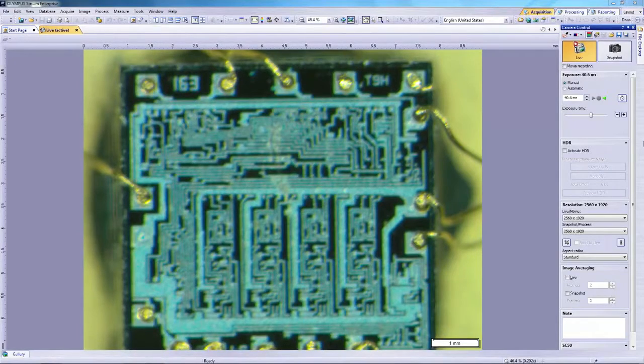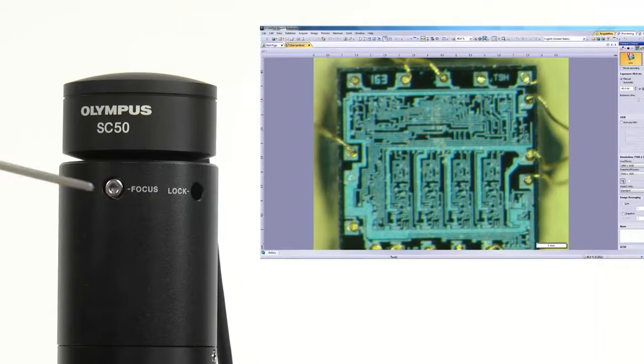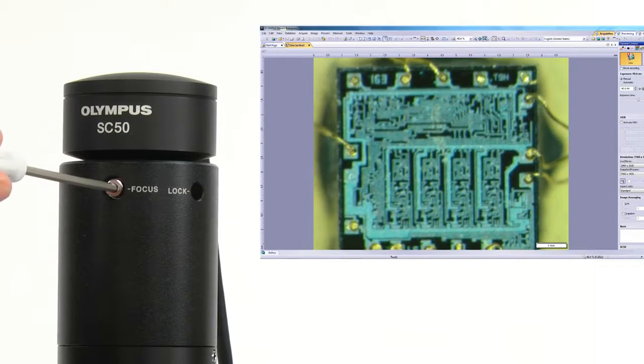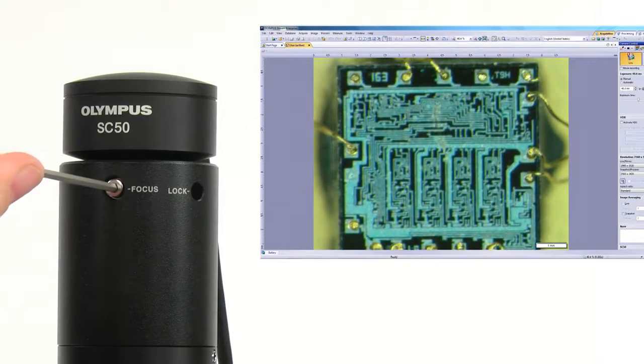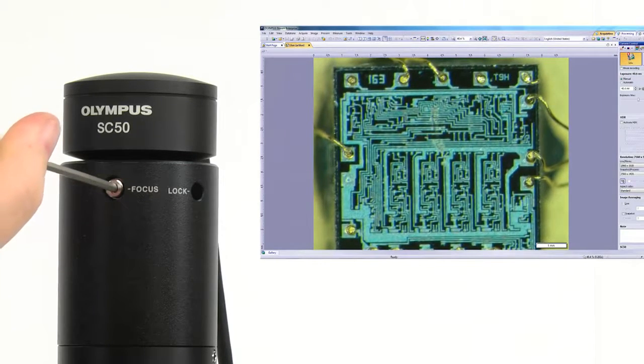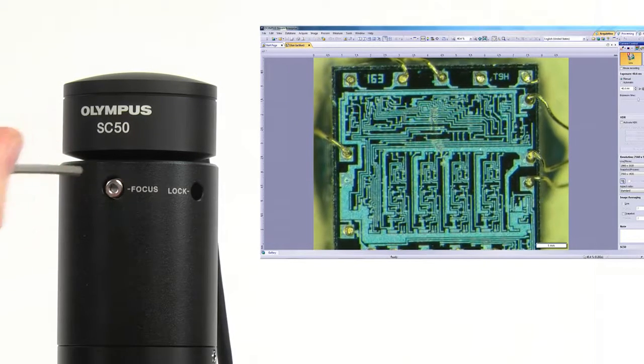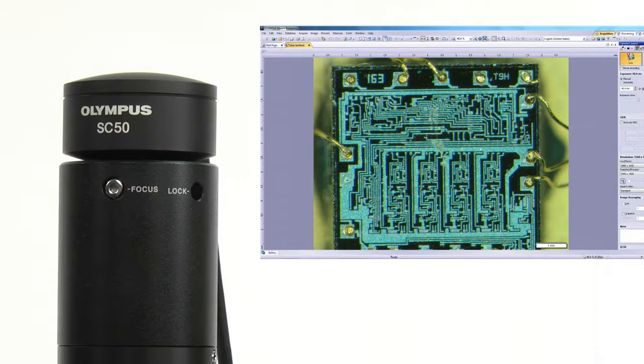Display the image on the monitor. If the image on the monitor screen is blurry, a parfocality adjustment is required. To adjust, simply turn the focus dial on the camera adapter until the image on the monitor screen is in focus. If your camera adapter has a locking mechanism, lock it into place.